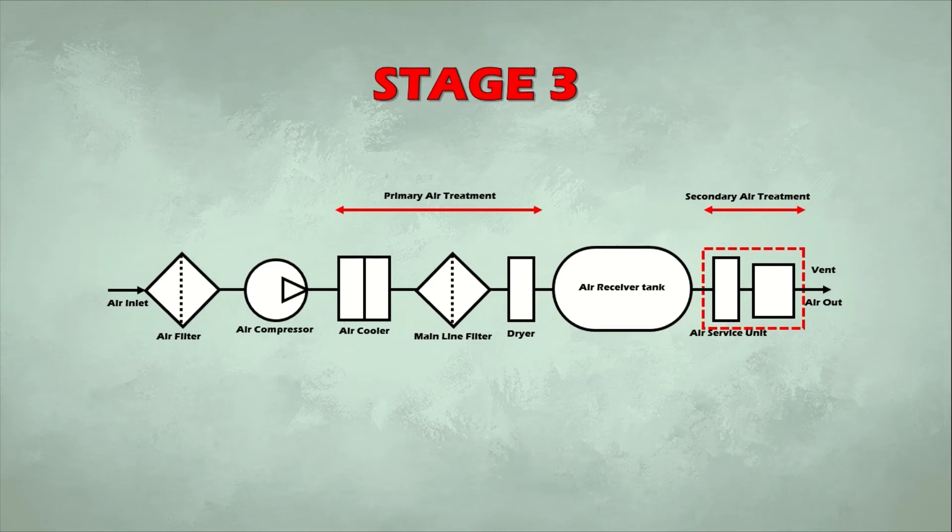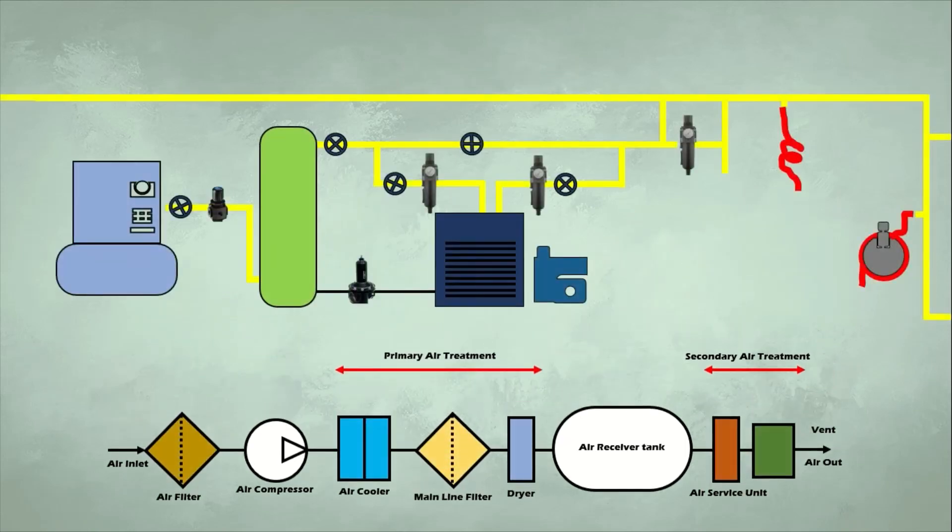In the third stage, the secondary air treatment process, further filtering is carried out. A lubricator introduces a fine mist of oil into the compressed air, which helps lubricate the moving components of the system to which the compressed air will be applied.